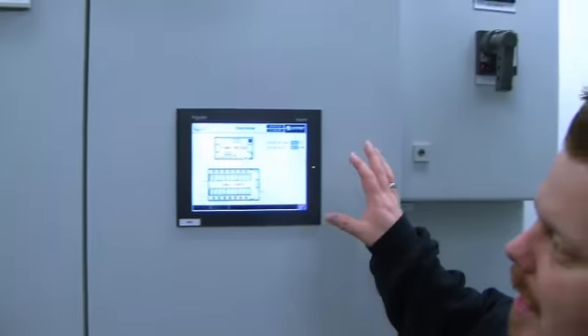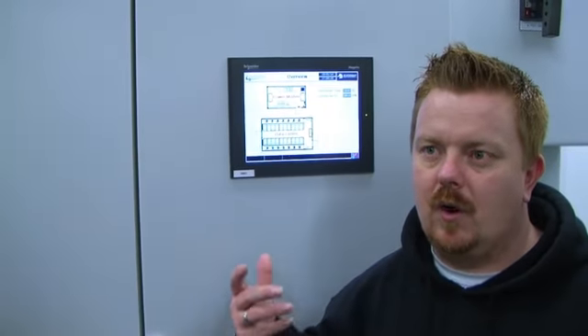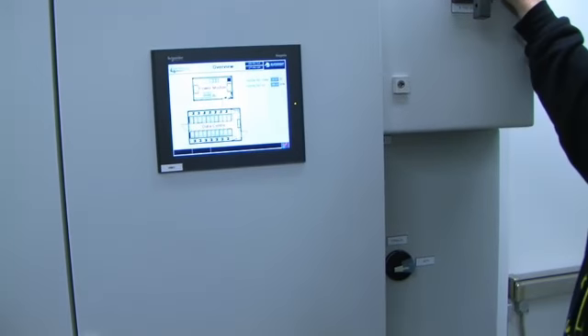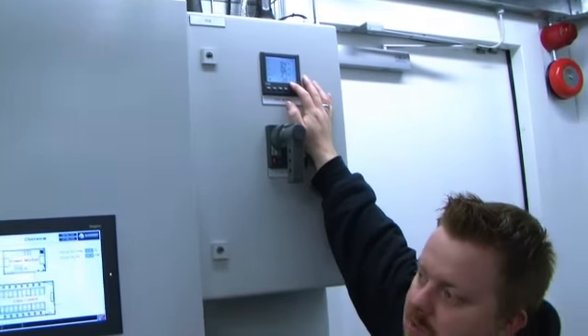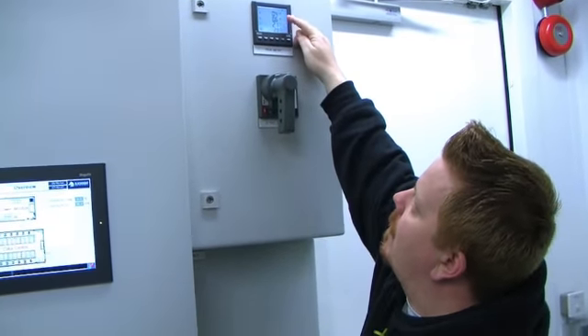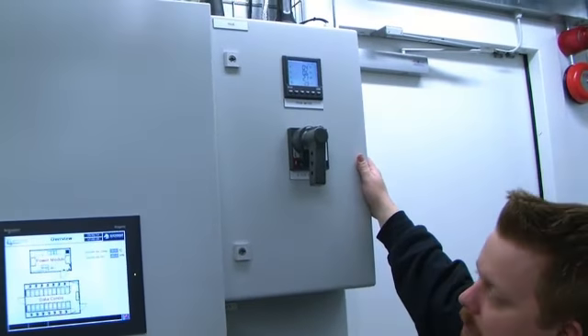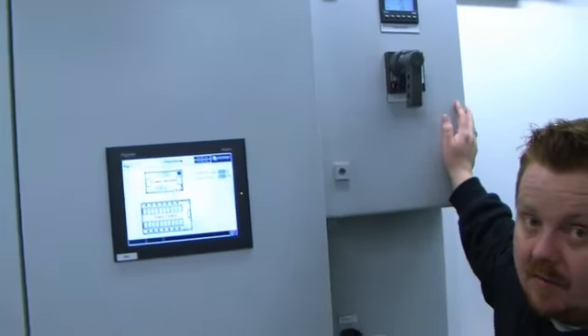In this cabinet here, I won't open any of the cabinets, but essentially we have an A and B fed fan board which controls all the fans in the building. And if A side PDU goes down, the B side fans go into an automatic emergency mode, and they'll ramp up. But it's not A and B in terms of fans. Every other fan is an A and a B fan. So in each side you have redundancy from a failure point of view, from a power point of view, and we have fail safes built in throughout. These obviously are power meters. They can tell us the current draw on each phase. So there's very little power actually being consumed at the moment, because the data center is in the pre-ramp up stages of having live equipment in it.